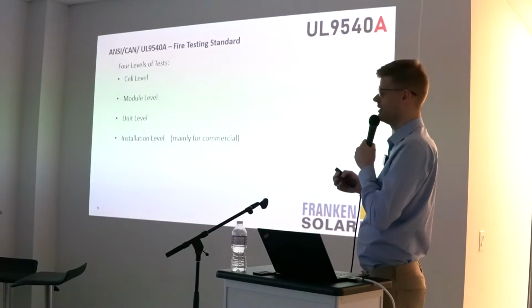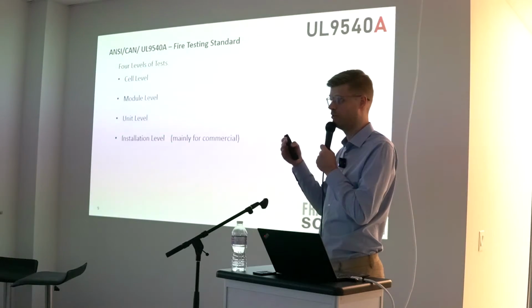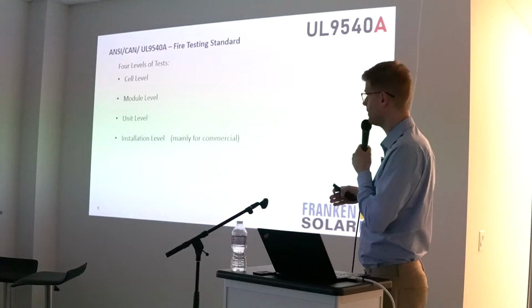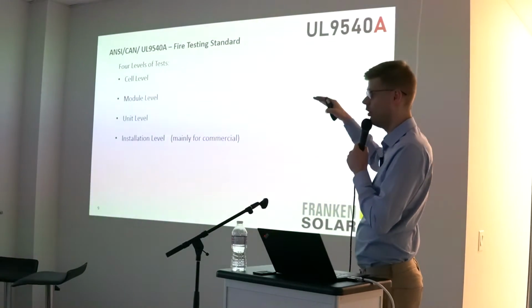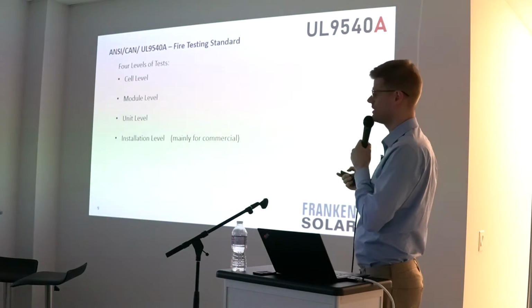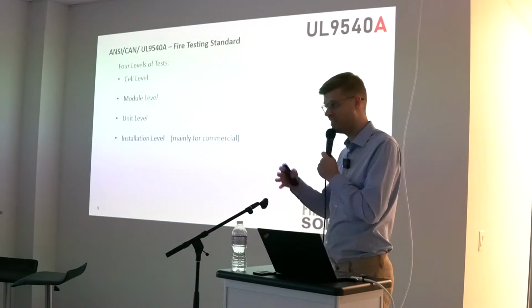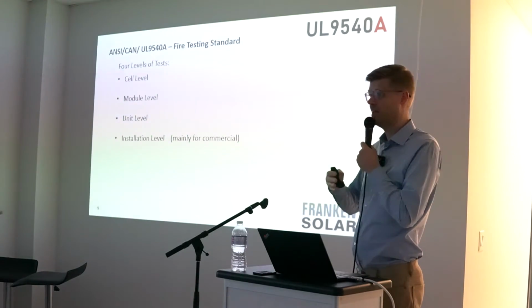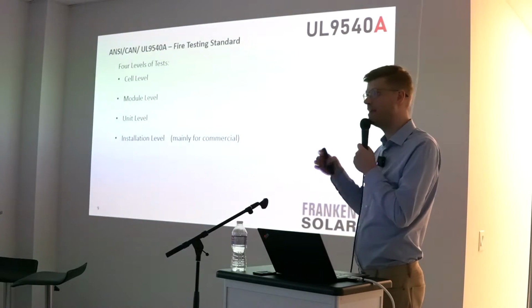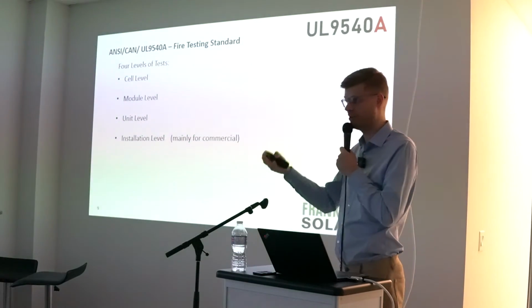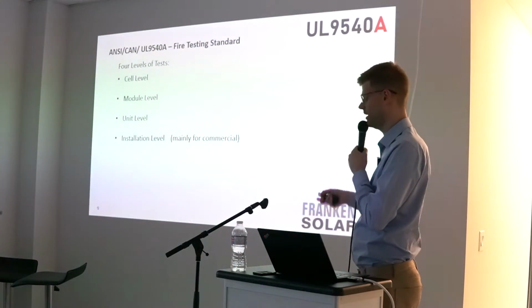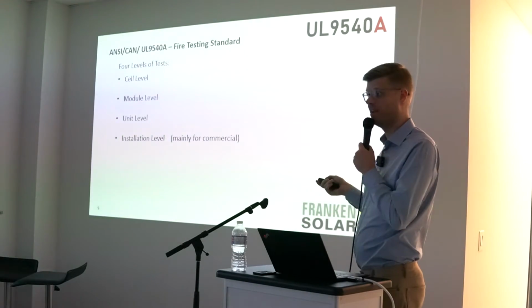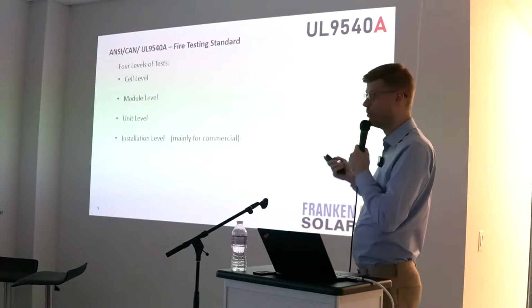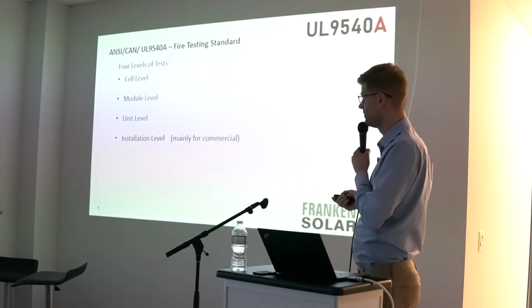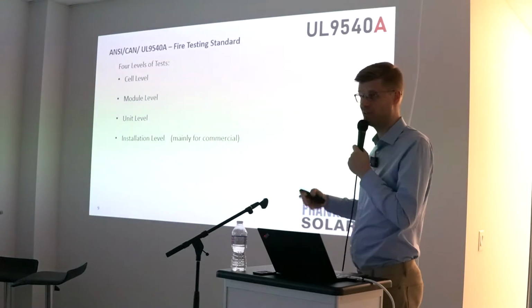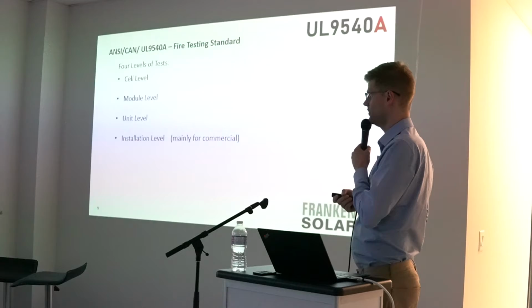And the important part is that currently all lithium-ion cells have a potential for thermal runaway on the cell level. And we will talk about the 4 steps of an energy storage system, and the fire testing is done on each level of the components. The lowest level, of course, is always the battery cell itself. So they take a cell, they test the thermal runaway by heating up the cell, and they measure exactly with a diagram, and we will see one a little bit later in the next slide, when that cell goes into thermal runaway, and that will be taken as a measurement for further testing when it comes to module, unit, or even installation level. So the cell is the lowest level, then multiple cells are typically packaged in a battery module, and then multiple battery modules typically form a unit, so an energy storage unit. And if you install multiple units in an environment like a containerized solution for commercial use, then you can also certify or test that system.